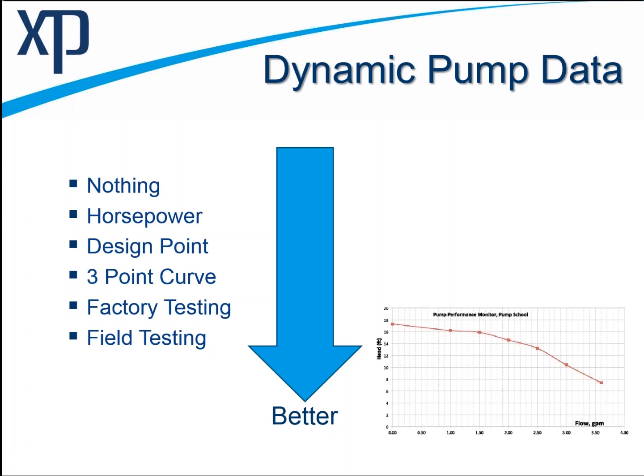Pardon me. So if you think about a pump, maybe think about yourself. Maybe a better example, you're lifting weights, so you're trying to lift a heavy weight. There's a certain weight above which no matter how much you try, it just isn't going to happen. Well, that's my example of the shutoff. So in this case, if I hit 18 feet of head, the pump isn't going to operate. Effectively, the system is pushing the flow down on the pump so hard that it just can't even turn over.